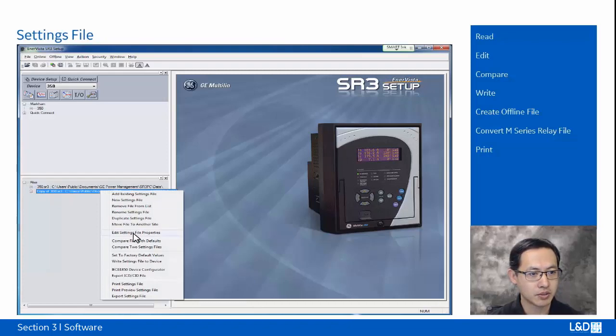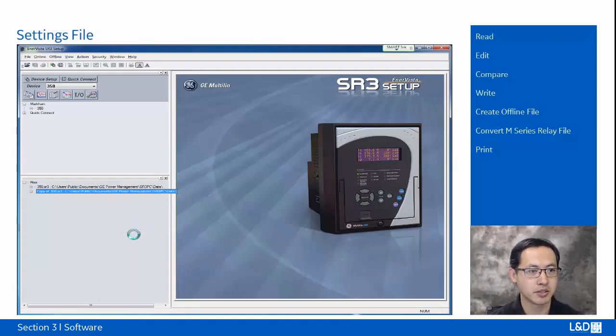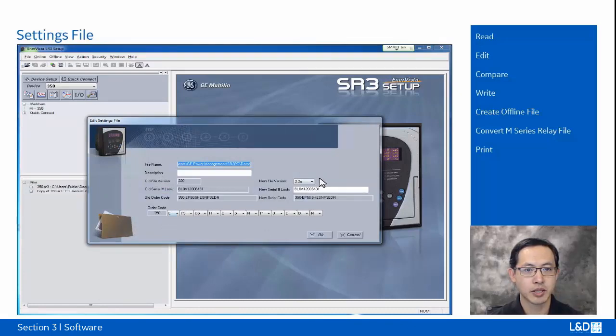Right-click again, we can choose Edit Setting File Properties. Under Editing, we can change the firmware number. For example, change 2.2 into 2.0, in order to upload this setting file into a lower version. We can change the serial number lock, which guarantees the download of this file only to a particular serial number. And we can even change the order code by using these editing functions. So just change the firmware version and click OK.